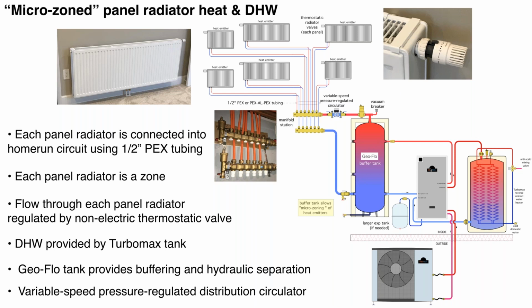So it could maintain a temperature range in the buffer tank, and that temperature range could be based on a set point. For example, we could turn the heat pump on when the buffer tank temperature drops to 100 degrees, let it run until the tank gets up to, let's say, 110 degrees, okay? Or that could be based on outdoor reset control. As it gets warmer outside, the temperature we're maintaining in the buffer tank goes down, and that would favor higher COPs out of the heat pump. So essentially, think of the heat pump as, I use the term battery charger.